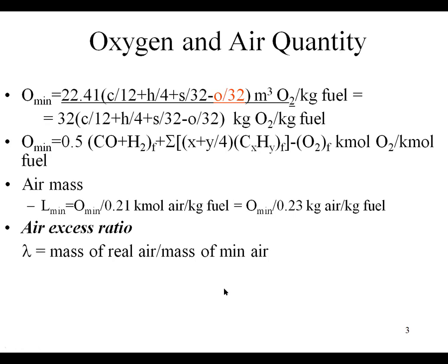In order to be sure that every molecule can run a combustion and meets the necessary oxygen content, we are using an air excess ratio, meaning in order to be sure that the combustion can take place, we will introduce more air than the minimum necessary.